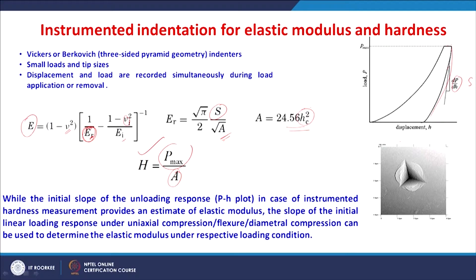For a perfect Berkovich indenter, A equals 24.56 multiplied by hc squared, where hc is the contact displacement. Knowing the maximum load applied divided by this area gives hardness as well. By instrumented indentation, both elastic modulus and hardness can be measured. The slope of the initial linear loading response under uniaxial compression, flexural, or diametral compression can also be used to determine the elastic modulus under respective loading conditions.